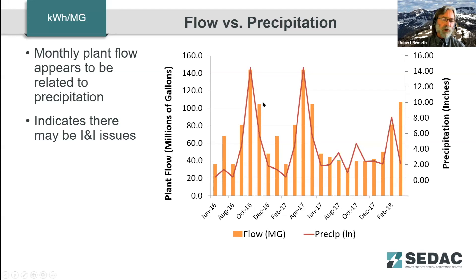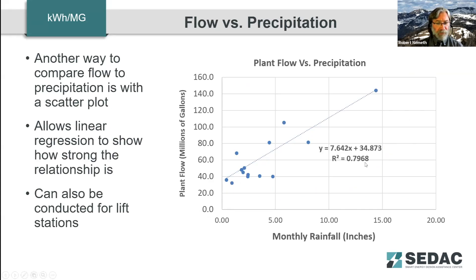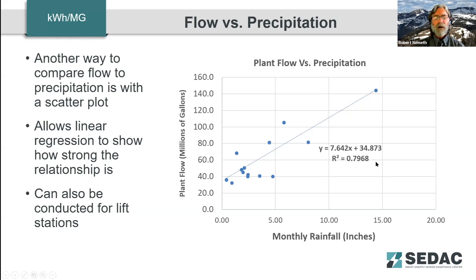We take the flow versus precipitation and chart that as well. Here we see a pretty strong correlation. On a scatter plot it's a 0.79 R-squared — call it 0.8. An R-squared of one is a line falling on top of the trend line, so 0.79 is a fairly decent relationship. That tells us there's definitely a relationship between how much rain falls and how much flow we're seeing in the plant. You could do something like this for lift stations too — compare energy consumption and rainfall for each lift station, and quickly identify which branch of your system is leaking more than others.